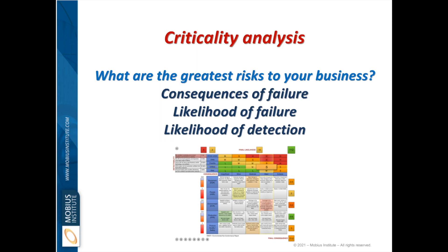But then the third part, which people don't always look at, is what is the likelihood of detection? I might have a piece of equipment that is unreliable, and the likelihood of it beginning to fail is reasonably high. This particular motor or piece of equipment is prone to failure. However, because we have condition monitoring, or because it always makes a lot of noise well before it fails, we will detect that it's happening and therefore we do not suffer the consequences.